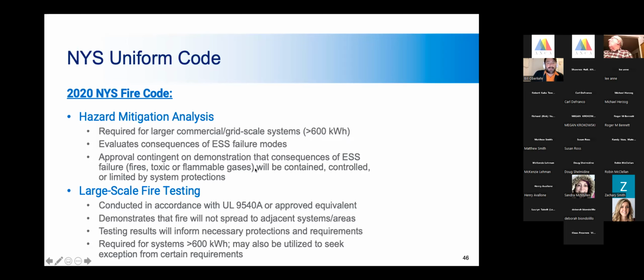The hazard mitigation analysis evaluates consequences of energy storage failure modes, and approval of the analysis is contingent on demonstration that the consequences of the failure, whether fire or gas, will be contained, controlled, or limited by system protections. So in addition to the large scale fire testing, the code, UL 9540A, we have a hazard mitigation analysis that essentially certifies this system can adequately respond to the worst that could happen within it. That's essentially what hazard mitigation analysis is saying.